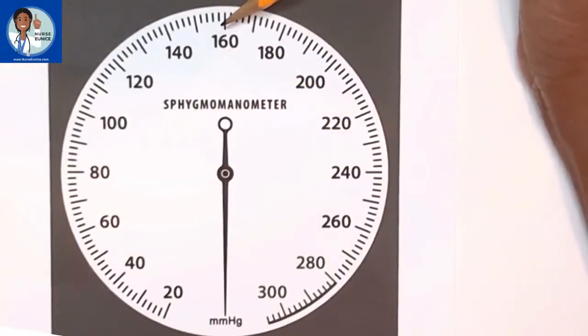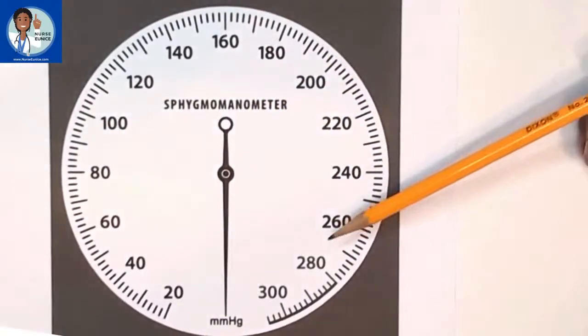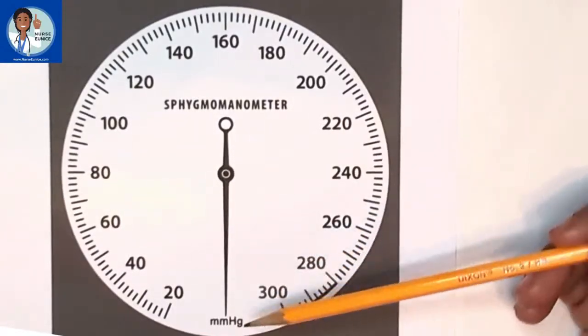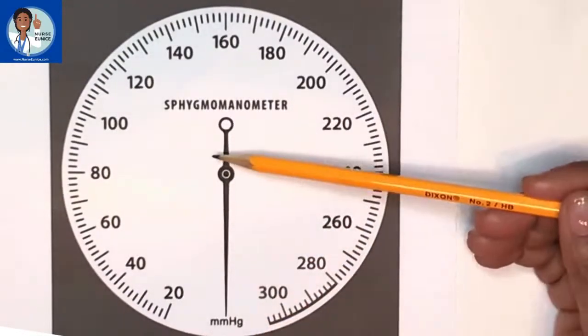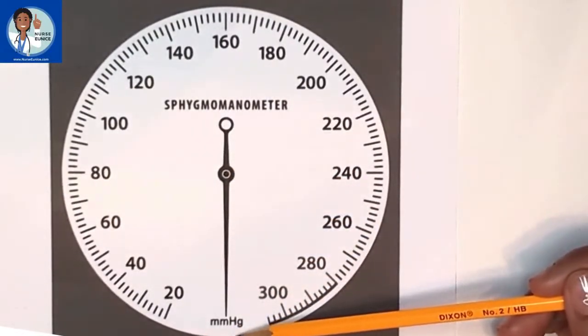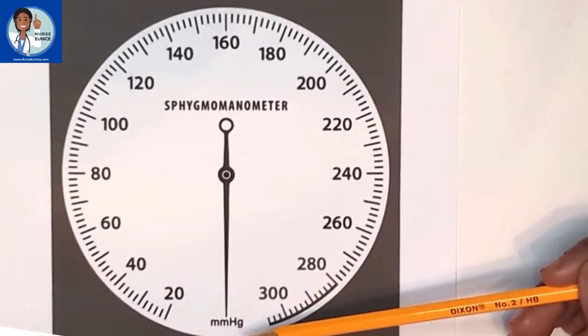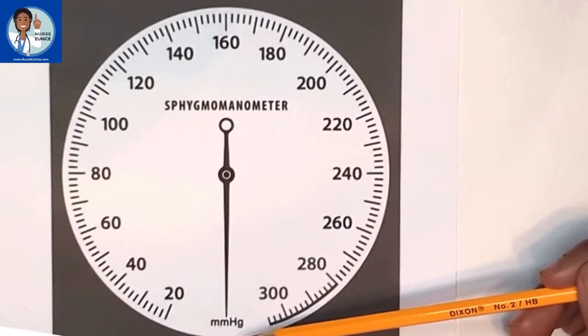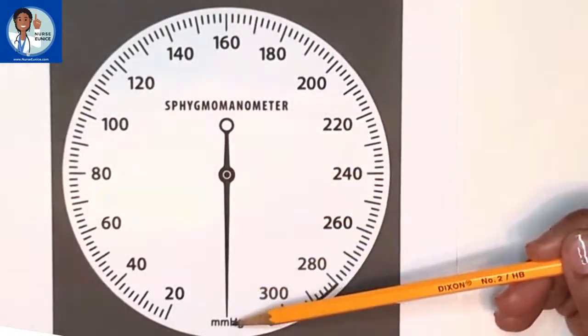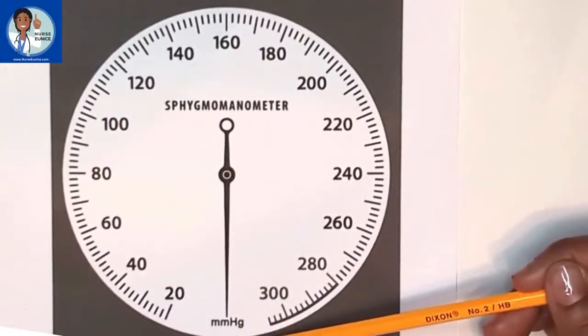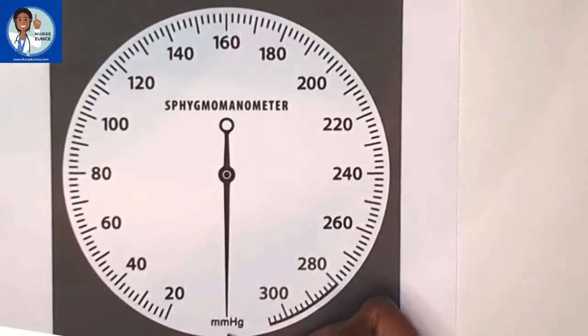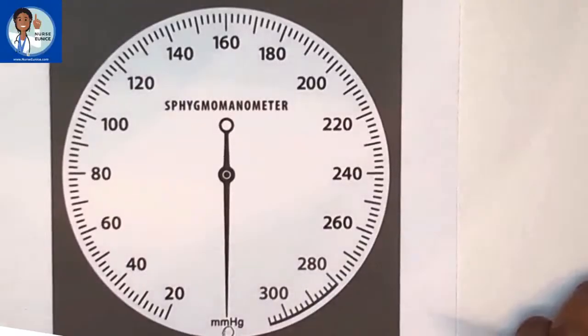In order for you to accurately obtain a blood pressure reading, you have to be able to read this gauge. If your gauge is calibrated, it's always going to start off here where it says mmHg, that's millimeters of mercury. That's how much pressure. We increase the pressure by actually squeezing on the bulb, and I'll show you that in a few moments. So our machine is calibrated, it's directly in the center at the bottom, which represents zero.